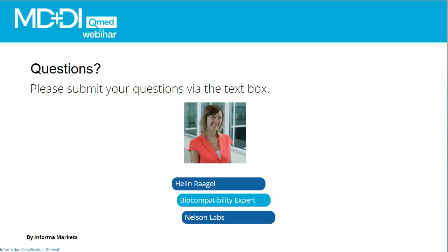But in this case, when we do recommend a dilution series and we see that the neat is cytotoxic, but then it starts to go away, which we expect to happen with dilutions, right? We want to show it in comparison to something else. Then we can really say, look, this is our device, and it has a cytotoxic reaction at neat concentration, but at 1 to 4 dilution it is already okay. But as you can see, a comparator product that is already on the market still shows cytotoxicity past that, right? And then you can prove that your device is actually doing better in the cell system, and with supplemental data from other testing that you might have, you can prove that this cytotoxicity reaction is not really going to be a concern.